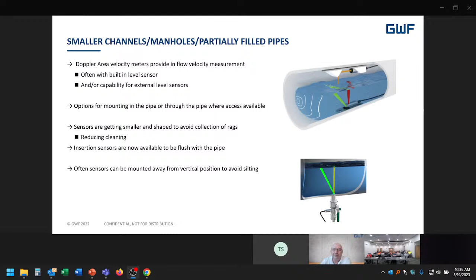Now, what about improvements in sensing for these? Many of these systems often use a continuous Doppler measurement. More recently, we're seeing a move towards pulse wave Doppler systems, where the system sends out a pulse of acoustic signal, and that is received back after it bounces off different particles within the water. Now, what is interesting about this is you're able to listen at different times for that received reply where it echoes back from a particle in the channel. Why is that important?